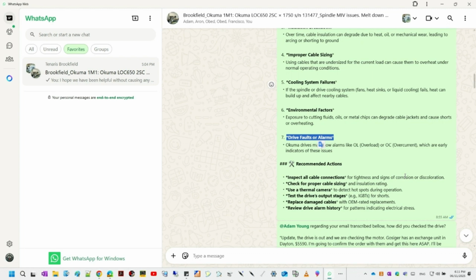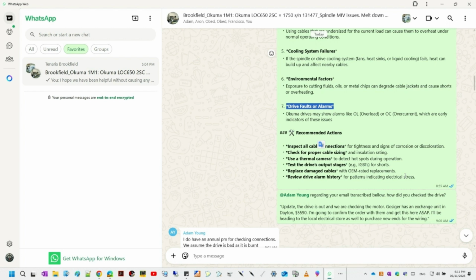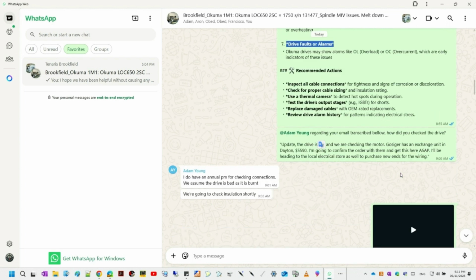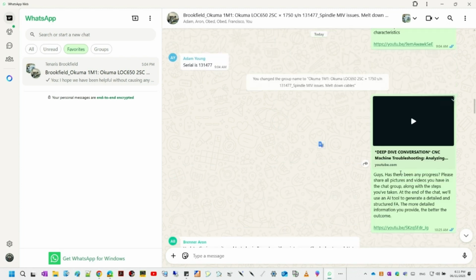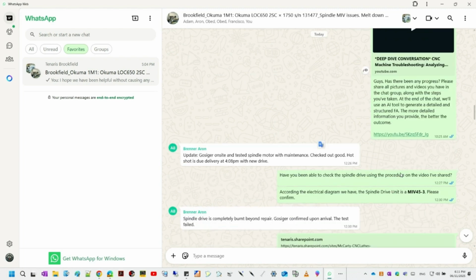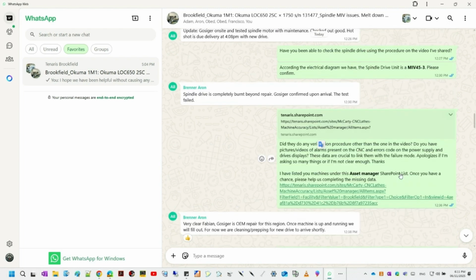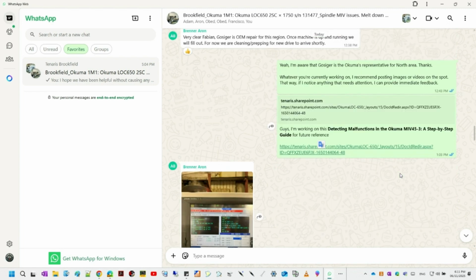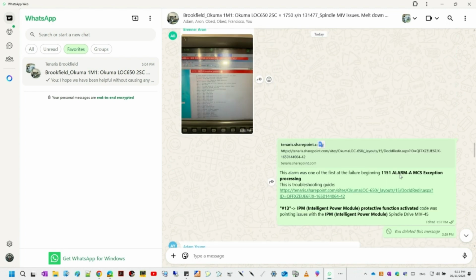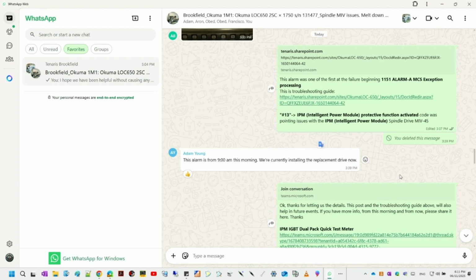I saw they even shared some video procedures for testing, emphasizing checking resistance between the U, V, and W output leads on the drive. Yes, they were trying to isolate the issue specifically to the drive unit, but the definitive confirmation really came from the on-site visit by the Gosiger service rep. The field service visit. Exactly. They validated, yes, spindle motor is healthy. And critically confirmed that the spindle drive itself was completely destroyed, burnt beyond repair. It failed their tests immediately, and they identified the specific unit, an MIV45-3.